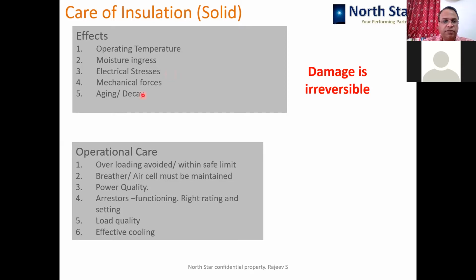So what can be done during the operation of the transformer is that overloading can be avoided, or kept within the safe limits. The breather or air cell are very basic equipment on the transformer, which, if maintained rightly, can control the effect of external moisture on the transformer insulation. Of course, the moisture generated in the transformer because of aging, you cannot control by way of breather and air cell. But a lot of moisture goes inside the transformer because of a poorly maintained breather or punctured air cell. So they are very easy to maintain, but they play a very important role.